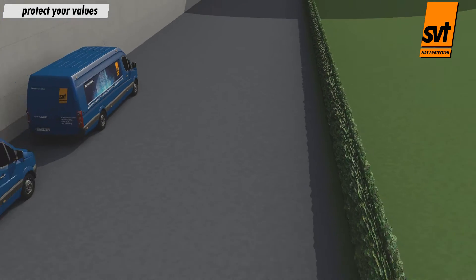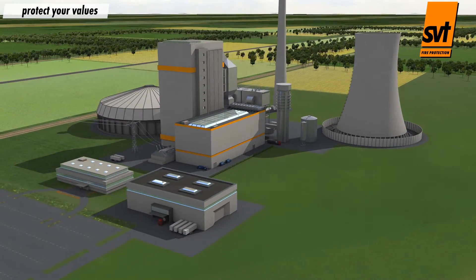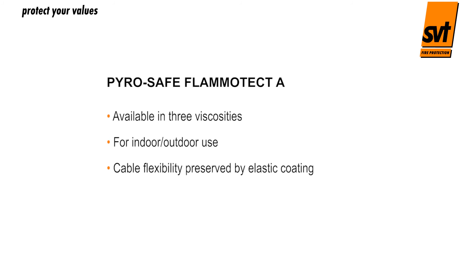SVT's PyroSafe Flammotect A cable coatings for indoor and outdoor use, or PyroSafe Flammoplast KS1 for indoors, provide effective and cost-efficient fire protection. Benefits include: easy application using a brush, paint roller or airless sprayer; coating of all types of cables without the use of primer; no electrical de-rating; cost-efficient application; solvent and halogen free. PyroSafe Flammotect A is available in three viscosities, for indoor and outdoor use, with cable flexibility preserved by its elastic coating and resistance to many chemicals.